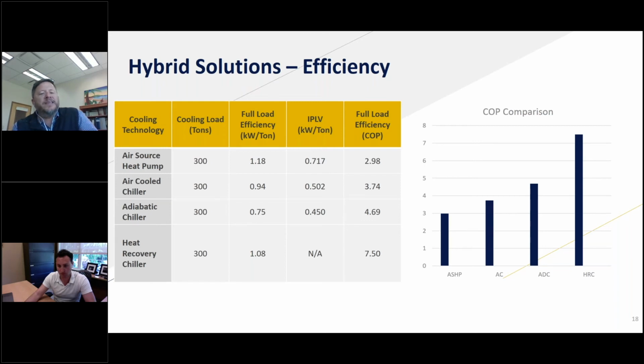But the idea is, with this, there's no cooling tower being introduced here. It really becomes either air source heat pumps or air-cooled chillers. So we're trying to compare like to like. But if you look at it, if I'm trying to make 300 tons of cooling and I don't have any heating load at that same time, as you can see, the least efficient method of doing that is with an air source heat pump. We have air-cooled chillers with different technologies that are far more efficient at just doing cooling.